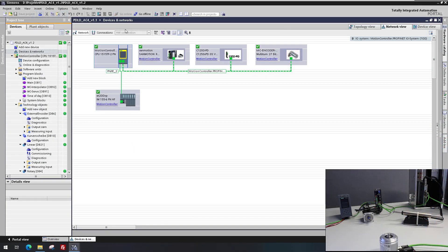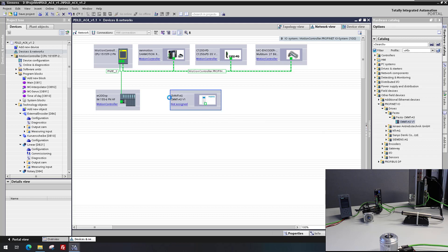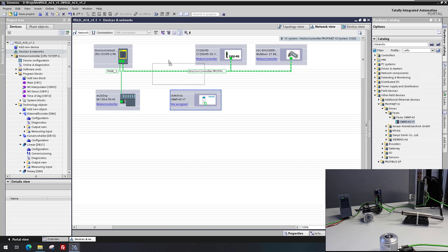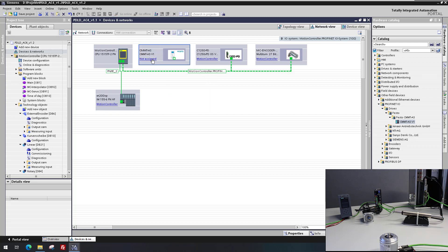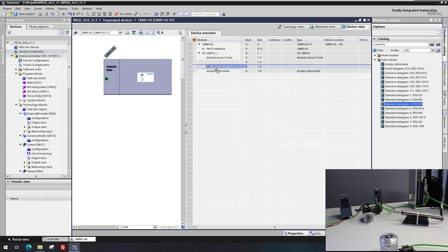If the drive device needs to be exchanged, it must be configured in the hardware configuration and interconnected at the technology object. The new drive device is inserted from the hardware catalog. The old one can be deleted. The drive device is then connected to the motion controller and the telegram configuration is adjusted. In this application class 4 example, the rotary axis uses Telegram 3.